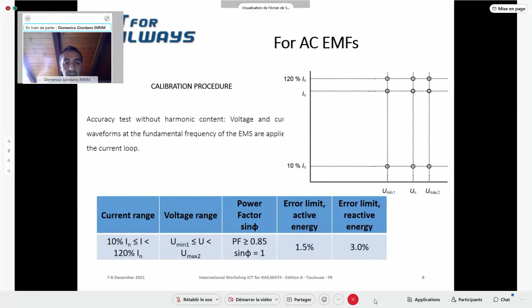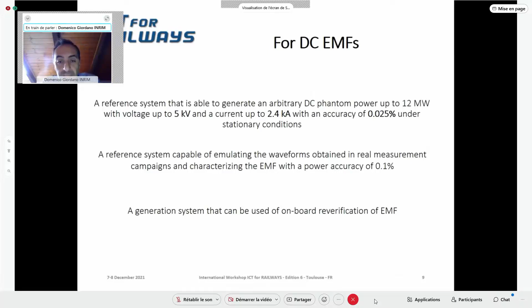Now we move from AC to DC systems. We developed a calibration facility able to generate voltage and current up to 5 kV and up to 2.4 kiloamps with high accuracy, and we are also able to apply disturbances like ripple to the generated signals.